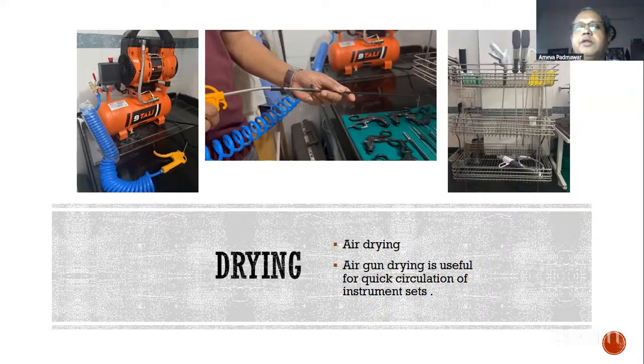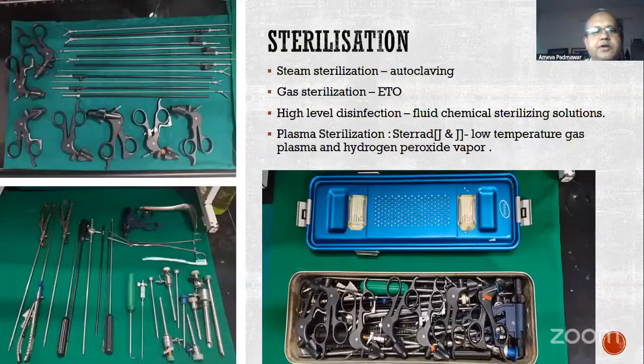A very good practice of drying hysteroscopy instruments is, after the procedure, to hang them up on your IV stands, because you cannot get rid of water which stays inside these thin, lean instruments by capillary action. Air drying, if you have such a small, very cost effective compressor, is good, but there are larger compressors available in the CSSD department, and they clean the inside of instruments very easily. It's a good adjunct to every laparoscopy center.